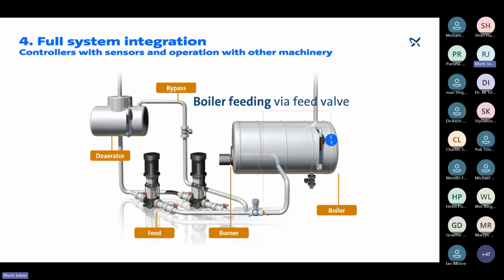Great. And then the last one would be your full system integration. And here we use controllers with sensors to operate in conjunction with other machinery within the system. So in front of you, you've got a standard and fairly common boiler feed system with boiler water level control, which is controlled by means of a modulating feed valve. And this is then tied back to and integrated with a level transmitter sensor output from the boiler. So your boiler is feeding back the level that it has at the moment and opening and closing the valve. The modulating feed valve is regulating your water intake, and this is according to your steam consumption.